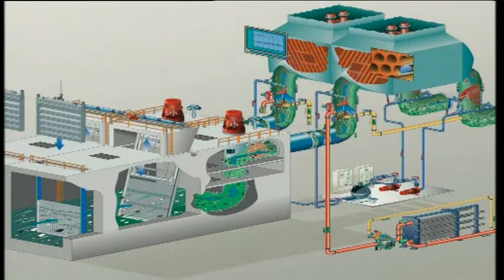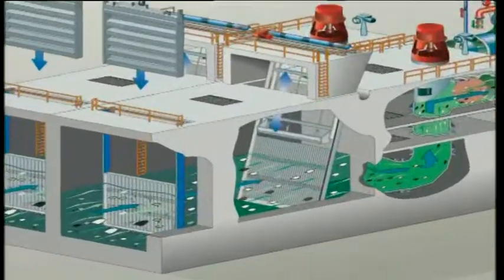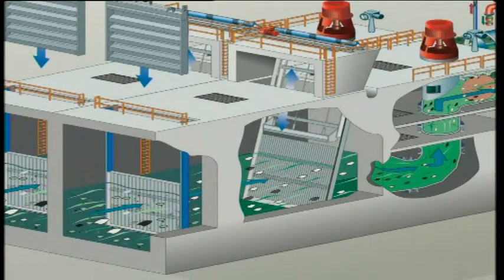Irrespective of the optimization achieved in cooling water pre-screening systems, Taprogge focused its research and development on the remaining components at the place of water extraction. Instead of using the traditional complex and maintenance-intensive intake structures, which physically take out debris from the water source, therefore subsequently requiring waste disposal, we completely reverse the approach. Wouldn't it be much more prudent to take out the water without the debris? Because debris that you do not take out does not require costly waste disposal.